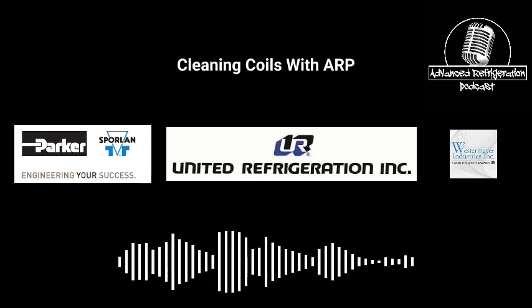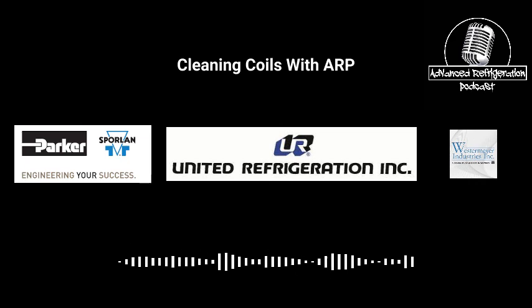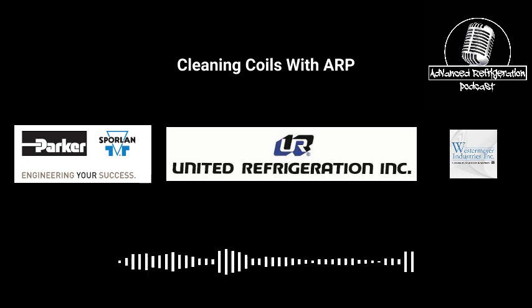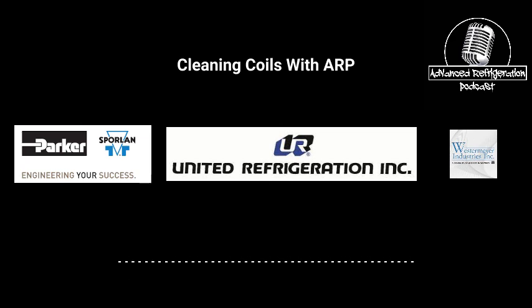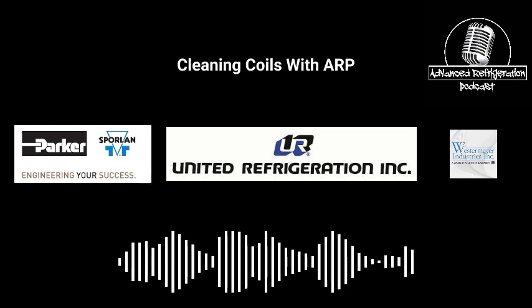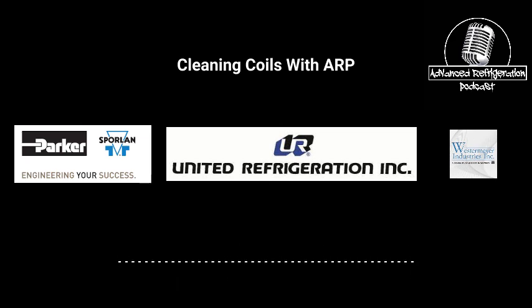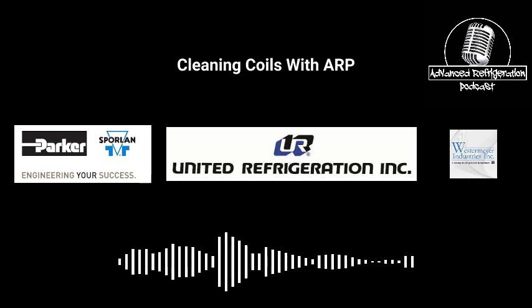Before you do the power washing, some people have a bag company come do all their power washing and they don't have their contractor do it. But if you're doing it yourself, I would rather power wash a coil myself. A couple things: a good high powered pressure washer, short wand, and then a swivel 90 at the end. That is the key to doing these.